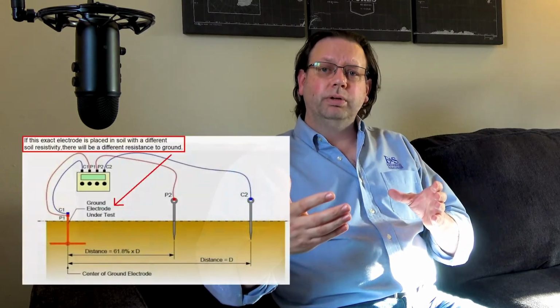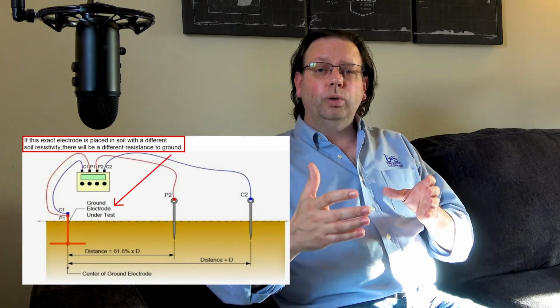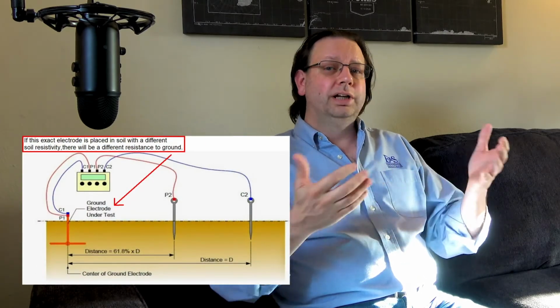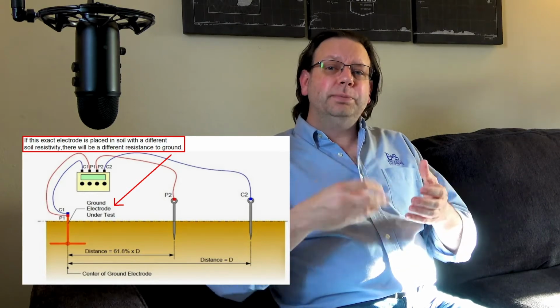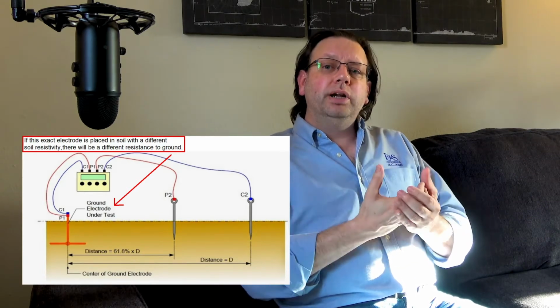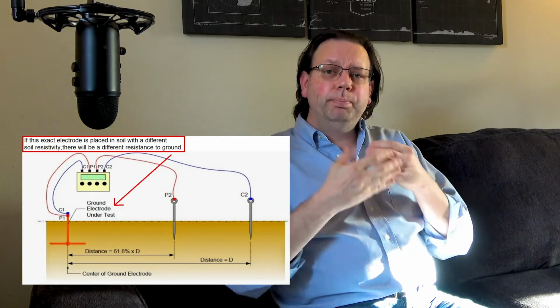So when you put in a resistance to ground spec, and you have a land area that's 10 foot by 10 foot, for example, if you're putting a spec, say 5 ohms, and you're sitting on solid rock, well, good luck. That's a bad spec, and whoever put it on there, I'm sorry to say, you did a bad job with your spec. There's no way you're going to achieve 5 ohms resistance to ground out of a single ground rod sitting on top of a mountainside. It's just not going to happen. You might be lucky if you get 1,000 ohms.